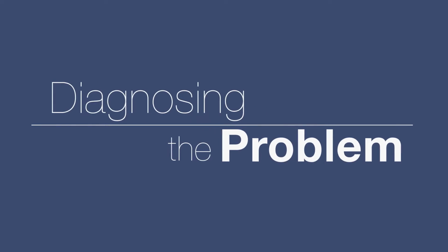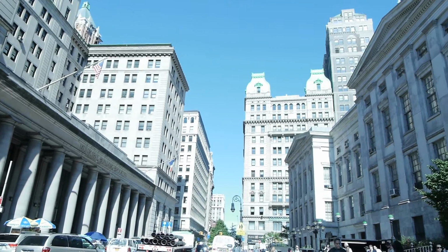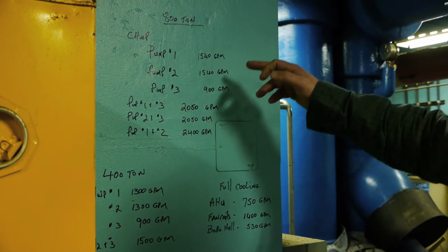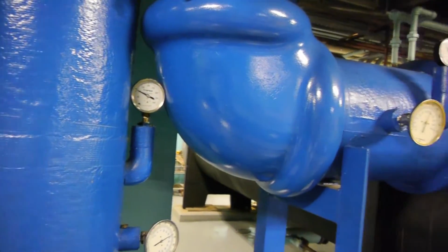The process was, we needed to discover the required airflow through our main three air handlers, and in doing so, we were able to go to a chart and calculate or add up the airflow, the CFMs, through each reheat. Once we realized the airflow that we needed, you're able to calculate your GPM. There's a simple formula. And so we went back to the main chiller plant. We put on an ultrasonic flow meter and we saw what we had on the primary loop through our primary pumps. Once we had our GPM available, then we were able to balance the two secondary loops and the loop for Borough Hall according to the flow that we had in the primary loop.